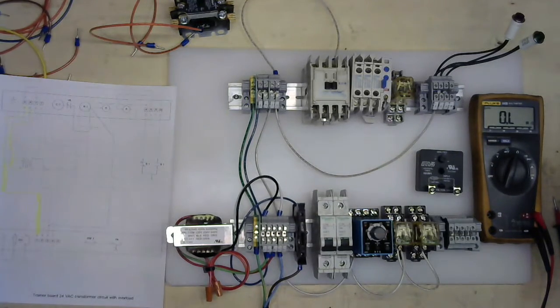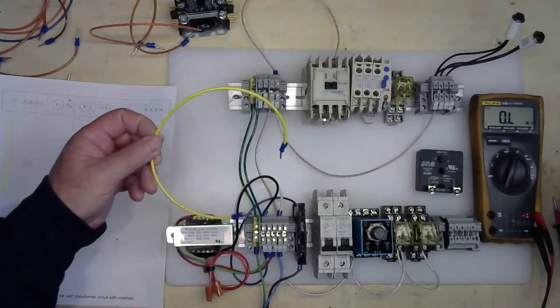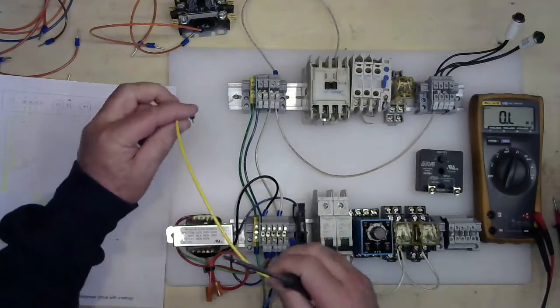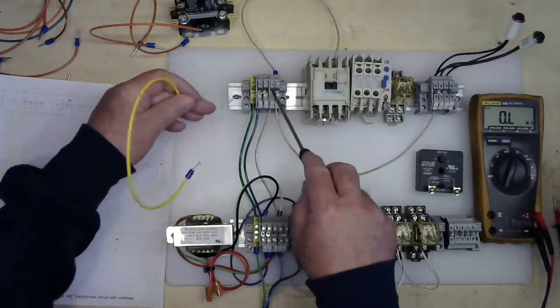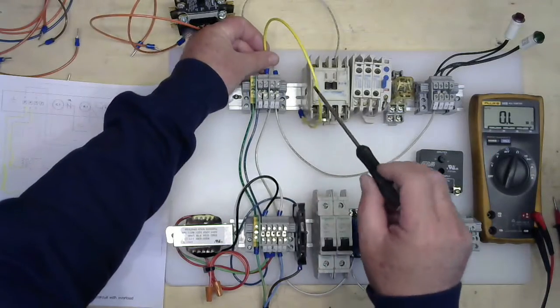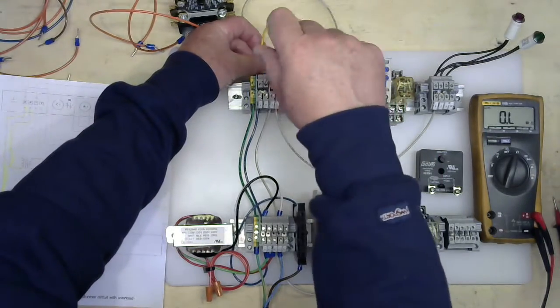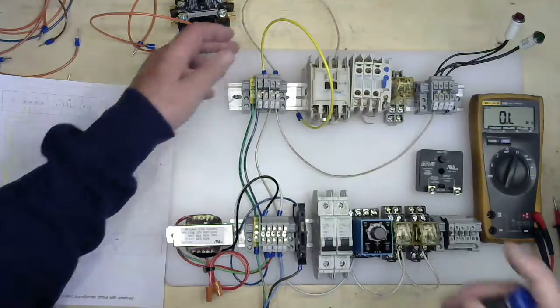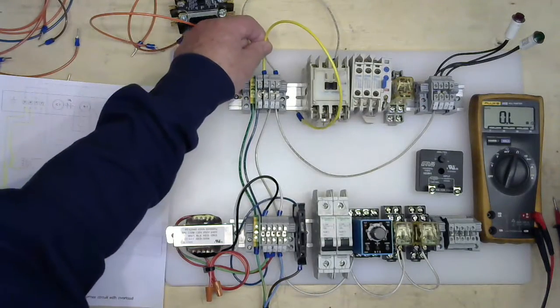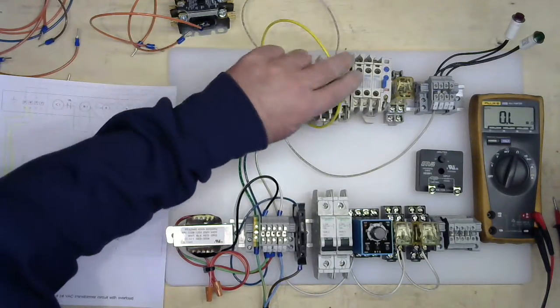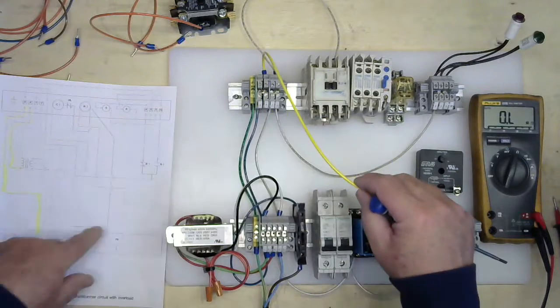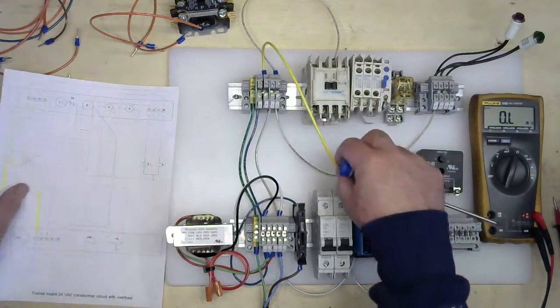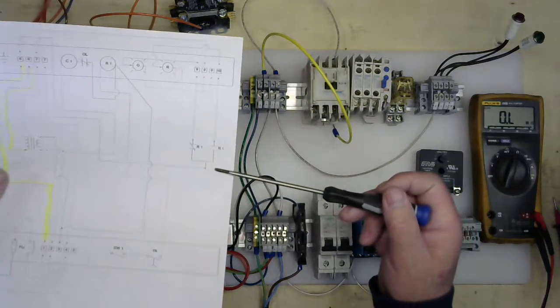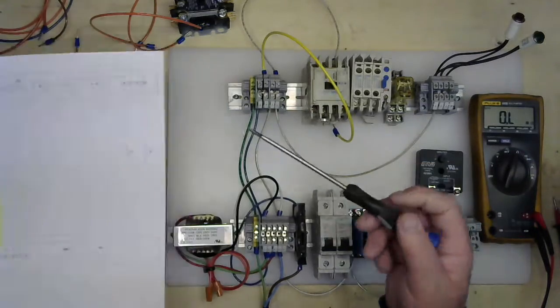So I'm going to take my jumper wire. I'm going to go from terminal 6. This particular one, I'm going to start on the back side of this terminal. When you put your wiring in your terminals, you always want to do a tug test to make sure it's in there snug and not coming loose. It's going to go into the common side of our relay.